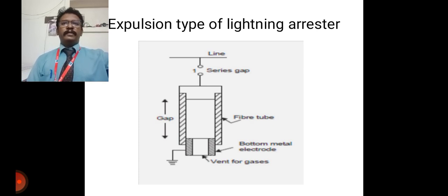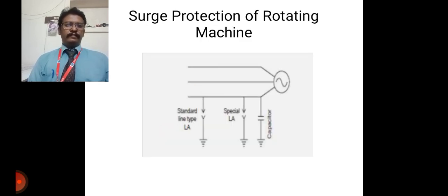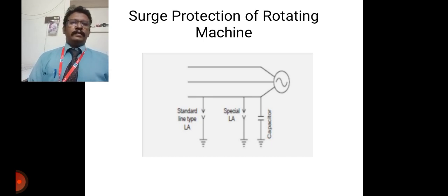Next, we are going to see about surge protections for rotating machines. So it is applicable for rotating machines. Even simply we can use it for arresting that particular low voltage. Normally, you can see here a rotating machine is less exposed to the lightning surges as compared to the transformer, because the transformer is exposed to the atmosphere. Because of the limited space available, the insulation on the winding of a rotating machine is kept to a minimum.